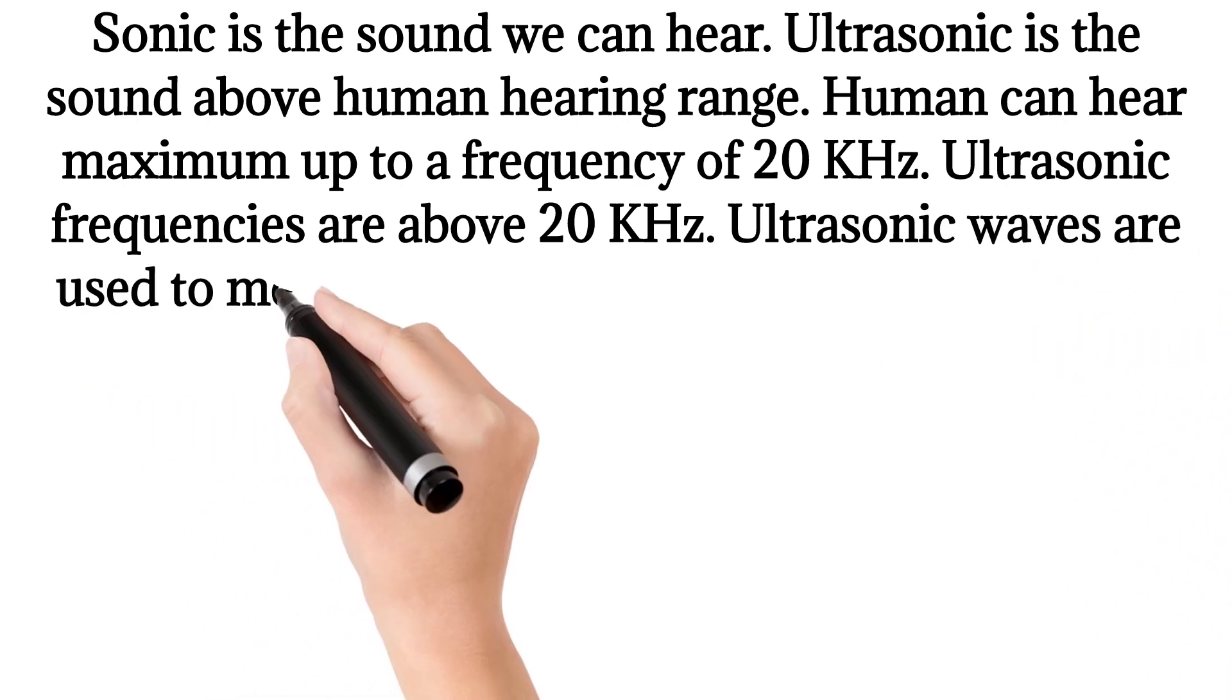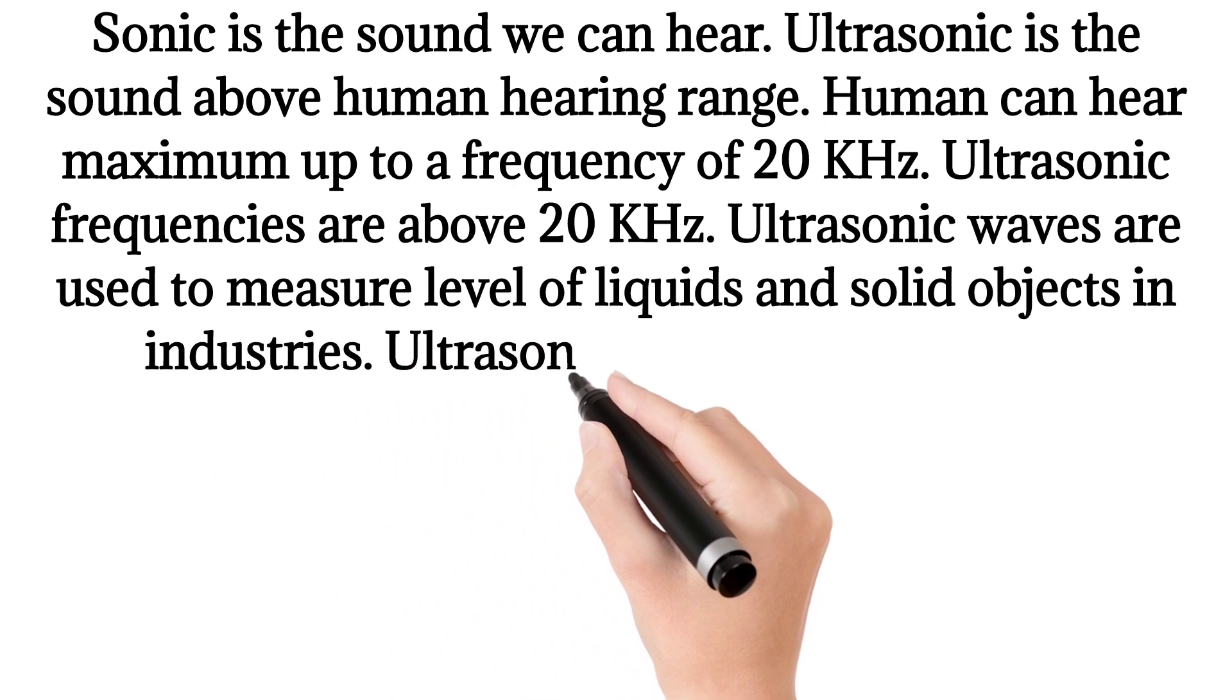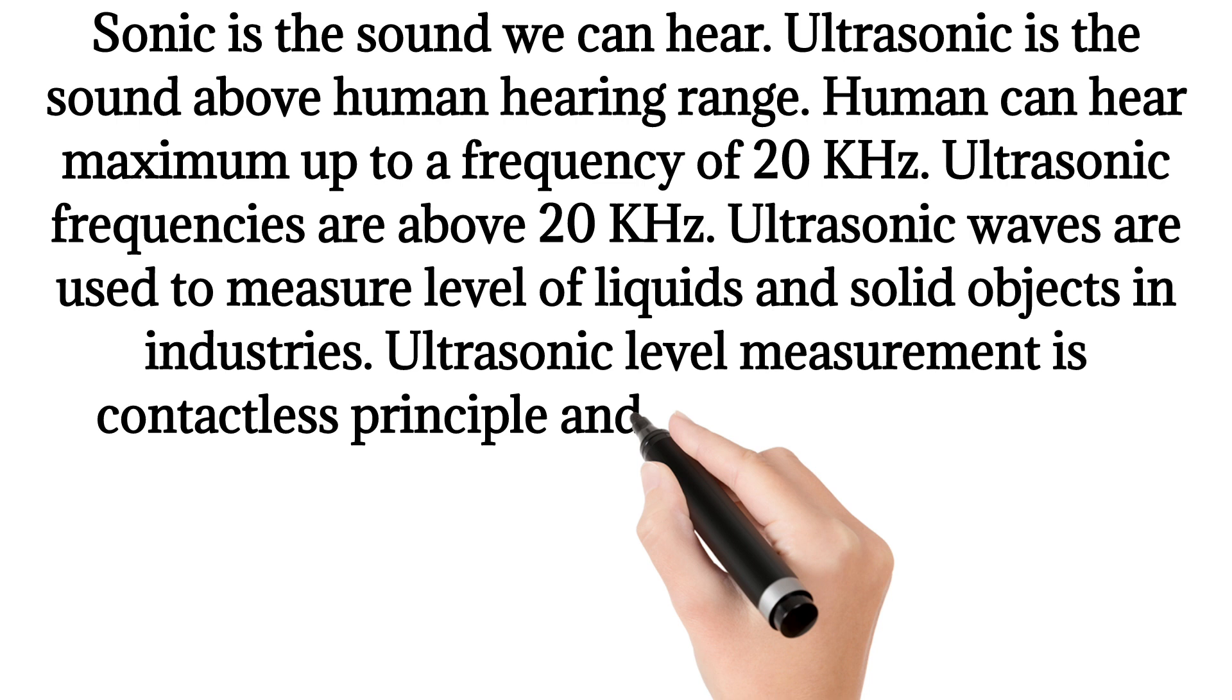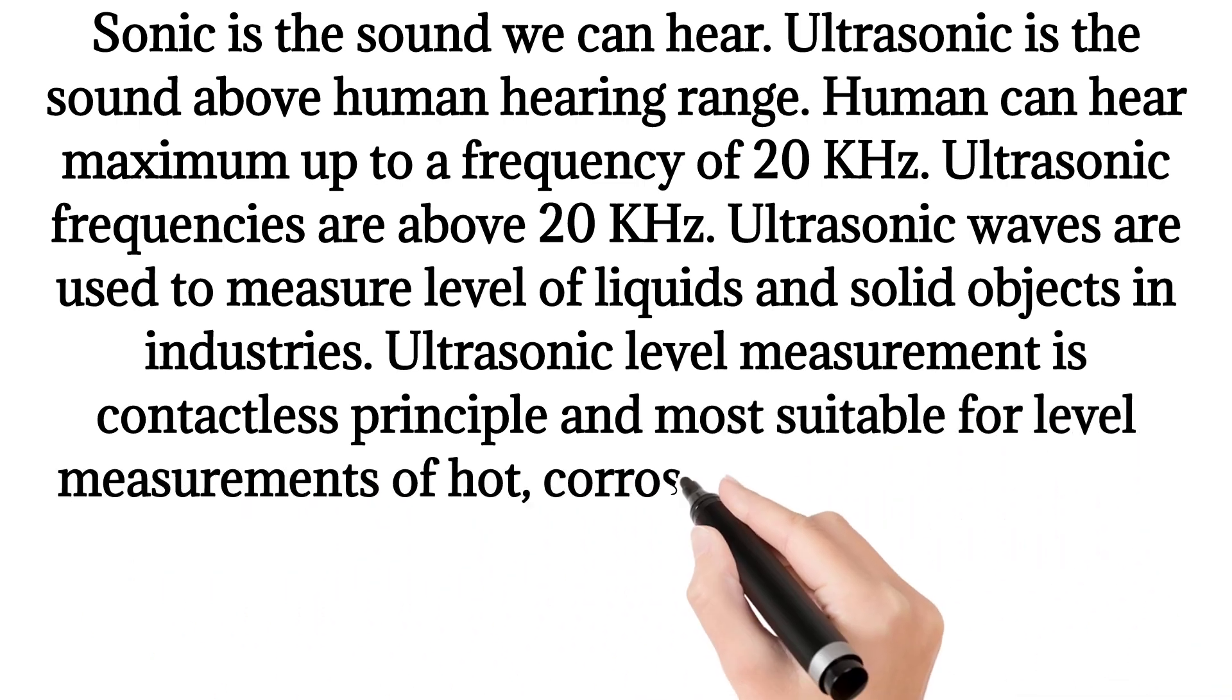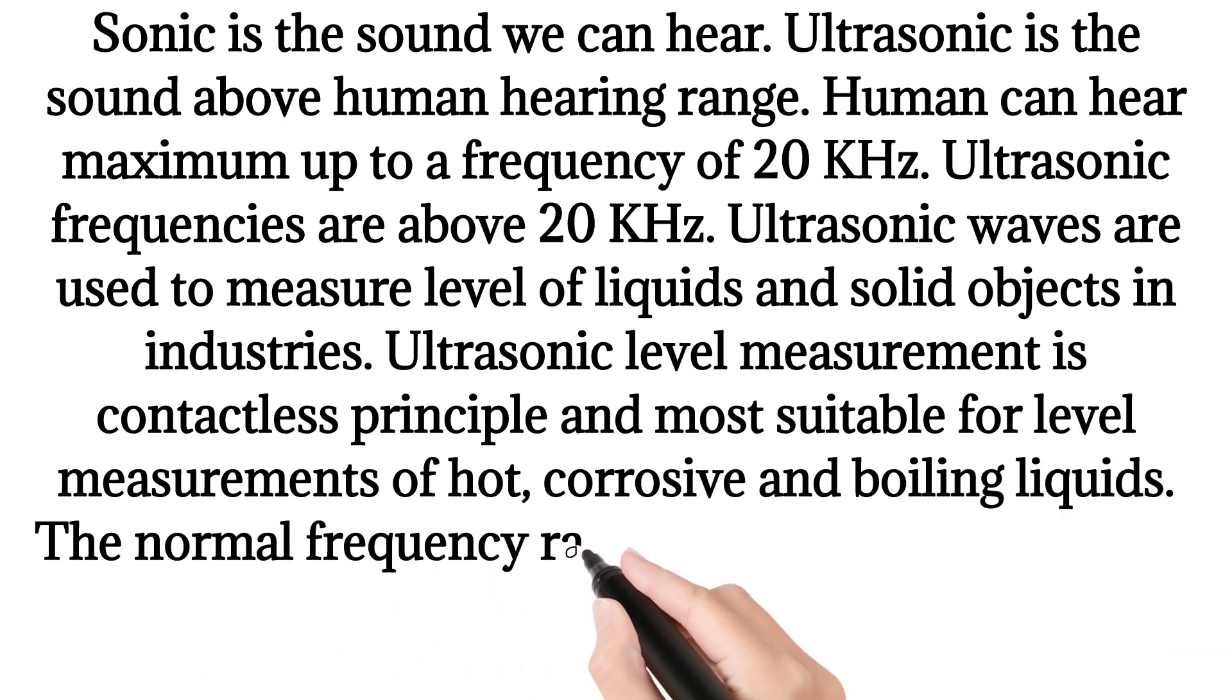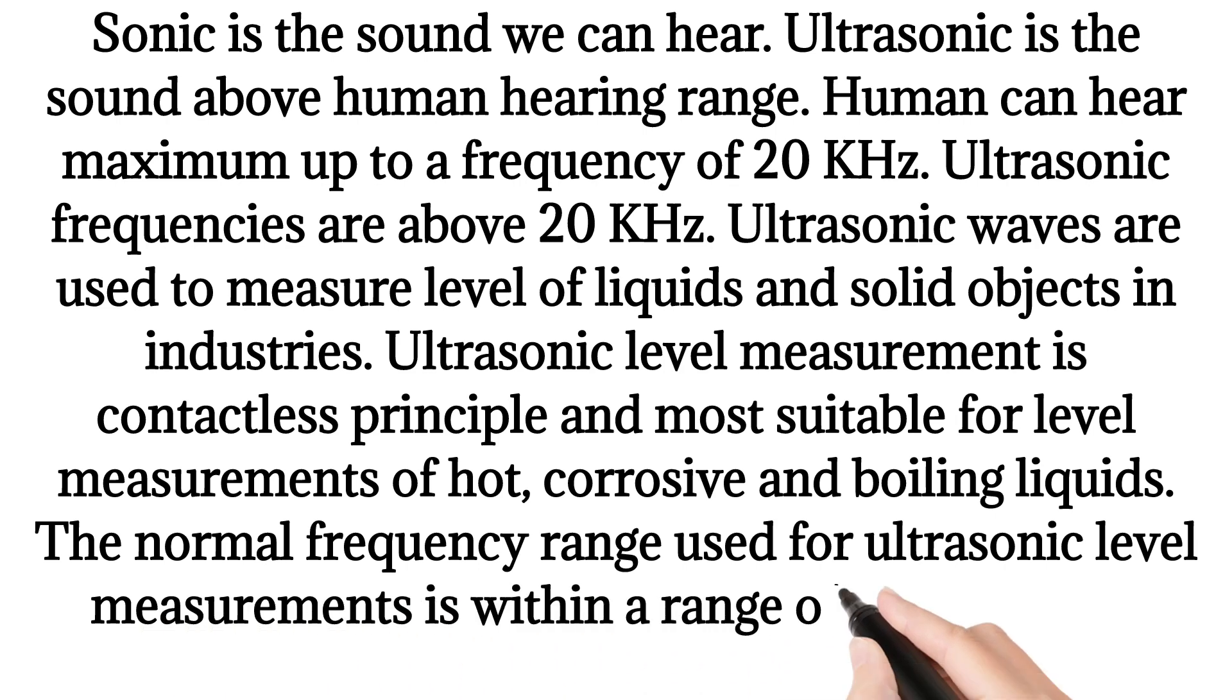Ultrasonic waves are used to measure level of liquids and solid objects in industries. Ultrasonic level measurement is a contactless principle and most suitable for level measurements of hot, corrosive and boiling liquids. The normal frequency range used for ultrasonic level measurements is within a range of 40 to 200 kHz.